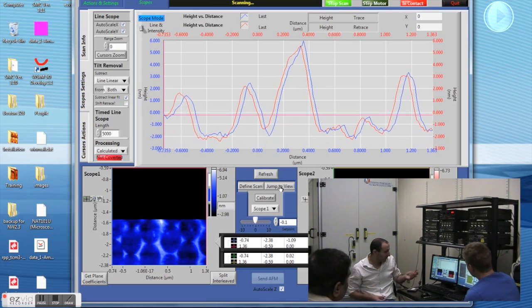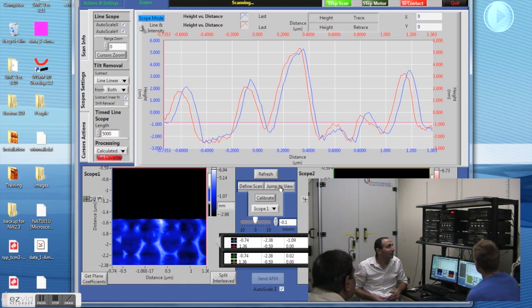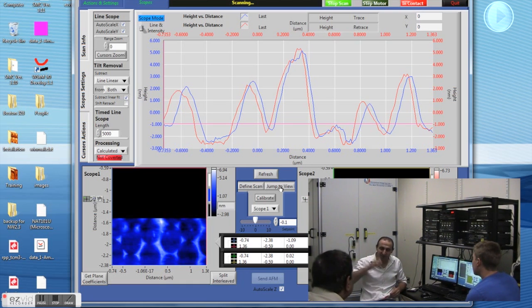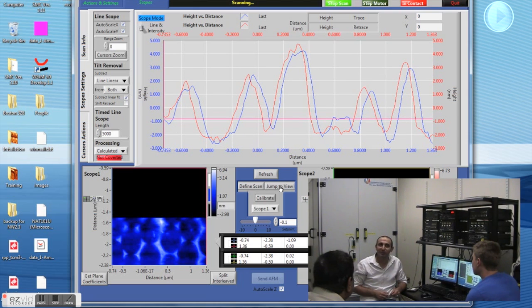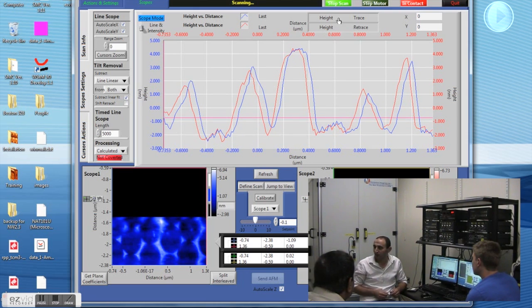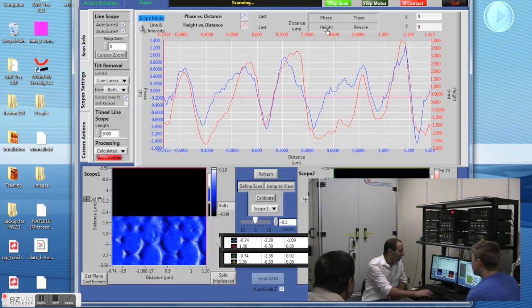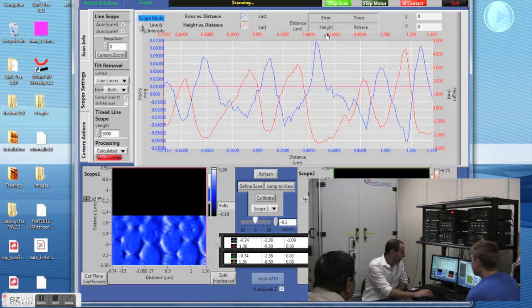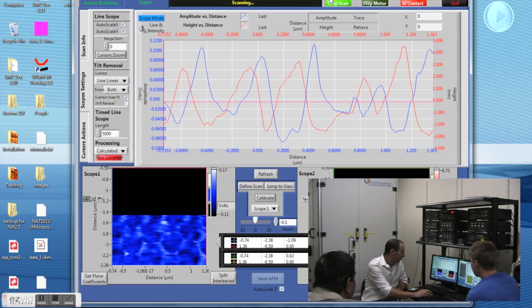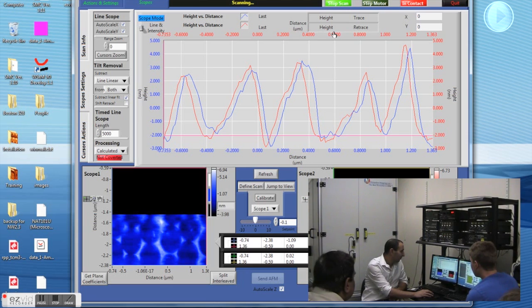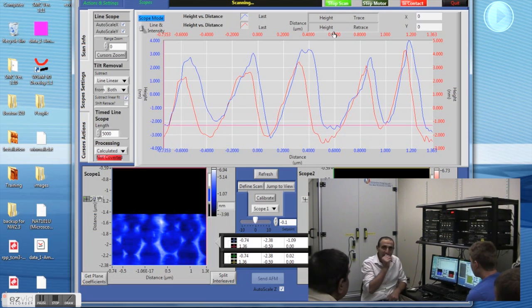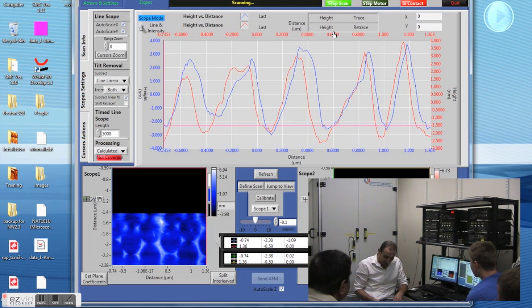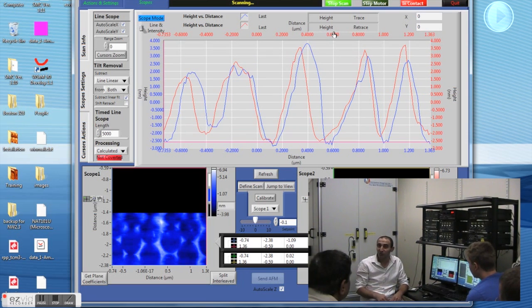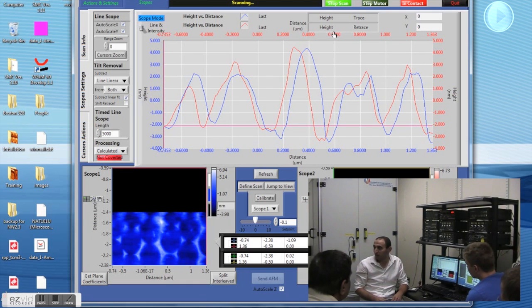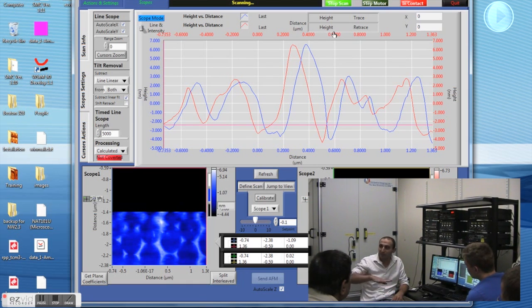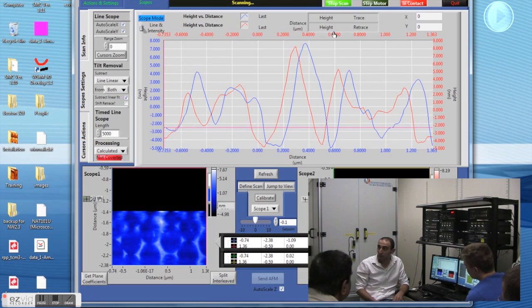Okay, so this is the AFM procedure. In fact, see, there's no optical alignment. Just simply pick and place the tip in there, and the tuning fork will do all that job. So this is the error signal, phase signal, which is signal to the error, in fact. And this is the amplitude. Amplitude will be nice, in fact, to monitor in structures like polymers and silicon. So you would easily see the contrast between the two different materials because of the amplitude decay on top of the polymer side.